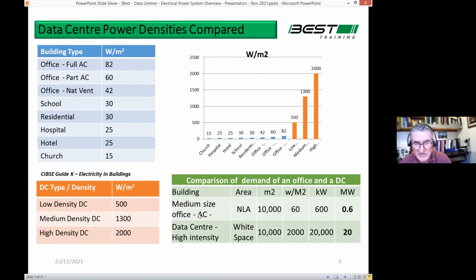So I've done a little comparison down here, different buildings. A medium-sized office with a net lettable area of 10,000 square meters, so it only includes the office space, the circulation routes, etc. It doesn't include the plant rooms. And for the data center we're looking at the white space. In a data center, the white space means the area where the data is actually processed. It's like the production line in the factory. It's where all the racks and the servers are. So it doesn't include the electrical plant rooms and the ventilation plant rooms, etc. So we compare them like with like, 10,000 square meters in each case.